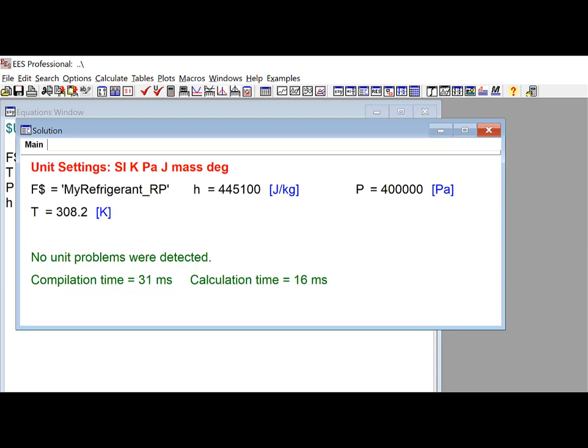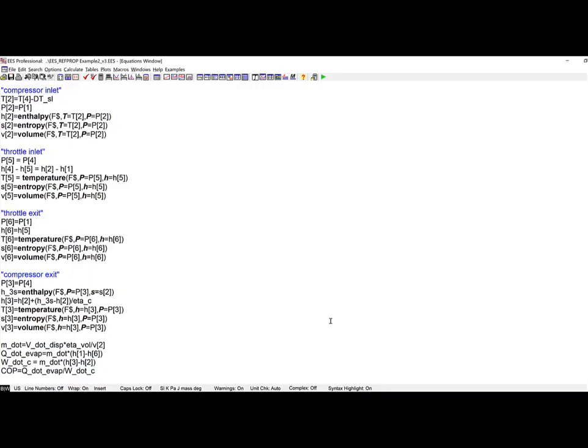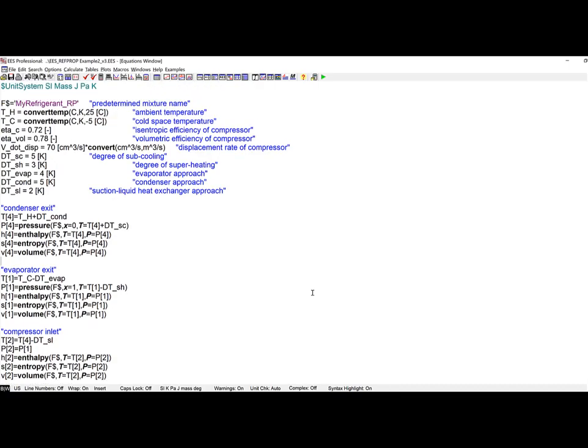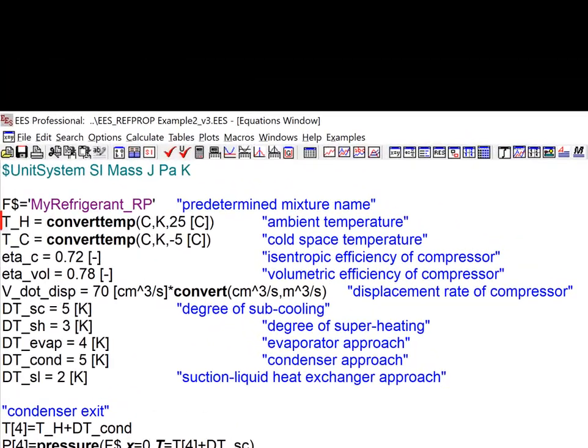Let's illustrate the use of this new EES RefProp interface by developing a simple model of a vapor compression cycle, which is shown here, that has a suction liquid heat exchanger. The refrigerant in the cycle will be that newly defined mixture, 40% R32 and 60% R125, defined with the MyRefrigerant.mix file. I just am going to select some operating conditions for the cycle, so the cold temperature of minus 5 and the hot temperature is 25 degrees Celsius.